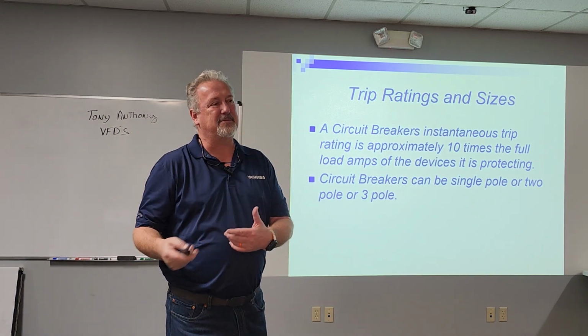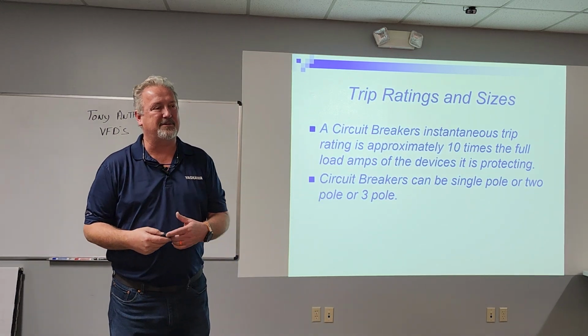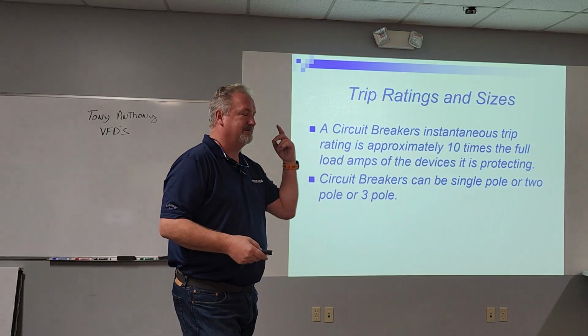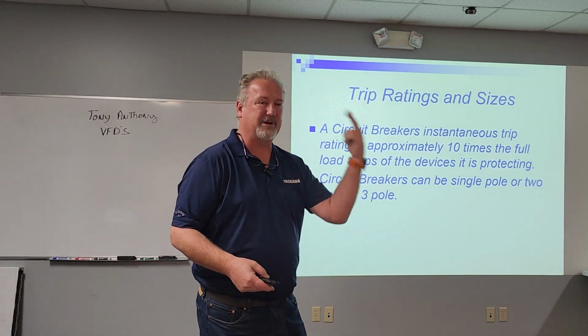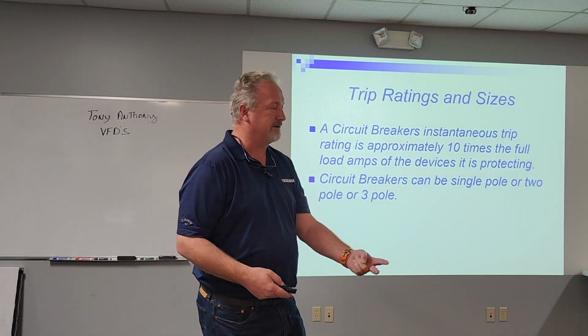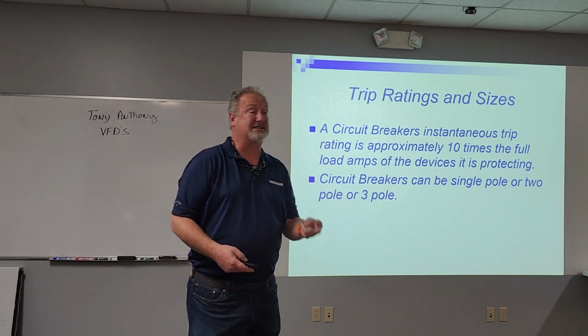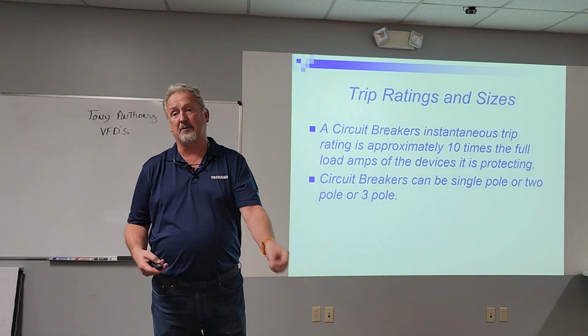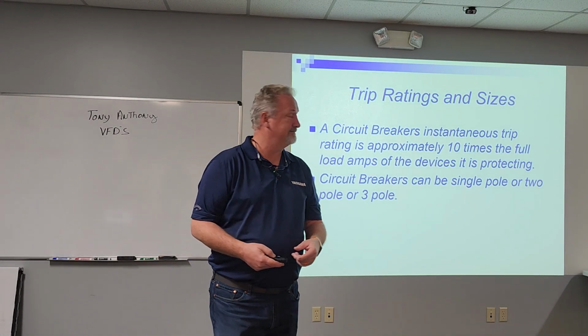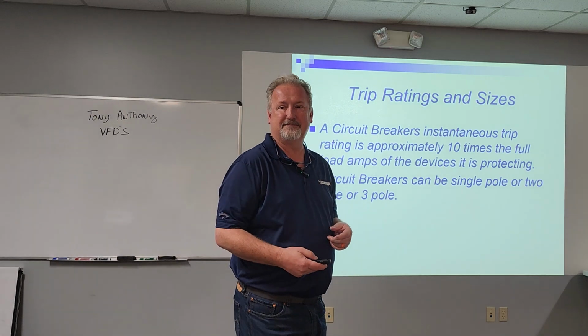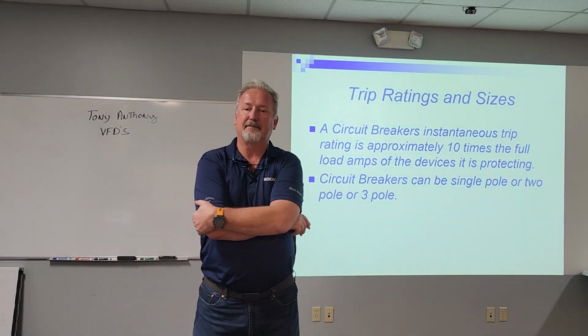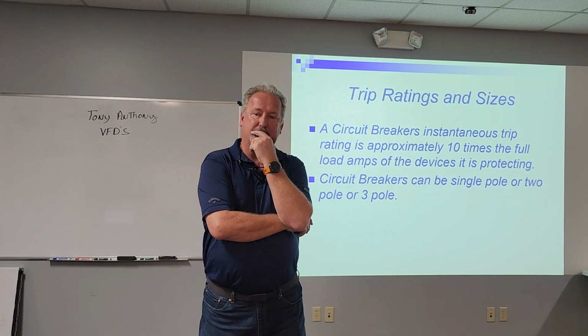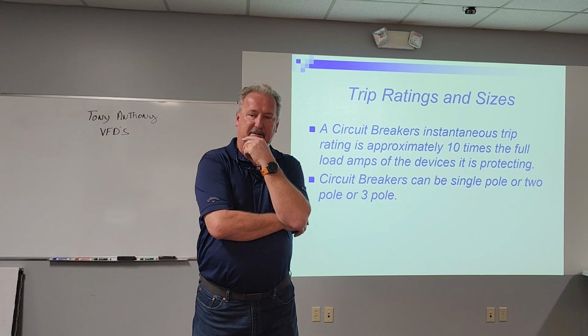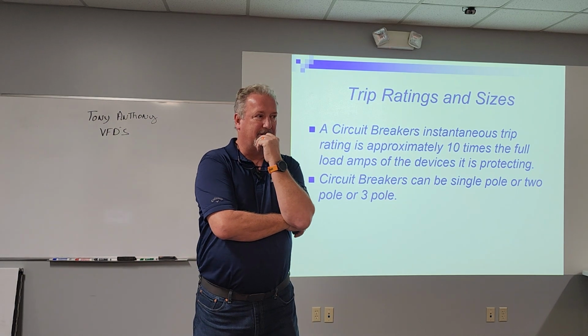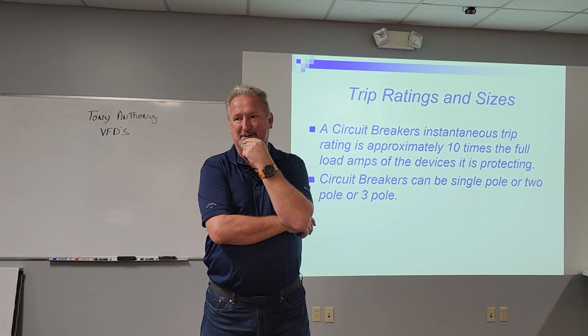So the key about breakers, and it's the same thing we're going to talk about in a minute with fuses: the biggest thing, make sure the connections are tight, retorque them if you come back to do maintenance later, and make sure you've got one that's designed for the type of electronic equipment you're protecting. On a breaker, what do you think the failure rate is? How many times can you reset it without it changing its parameters? On a breaker, that, actually, I don't know.